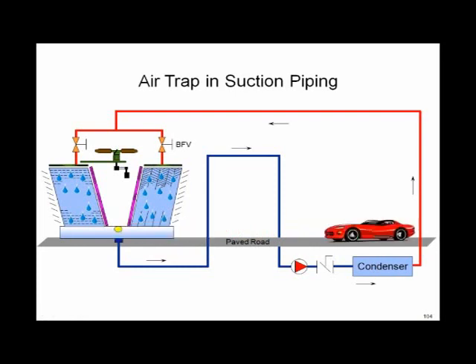I think you kind of got the idea, but the point is, we've got this piece of overhead piping overlooking the road and going back down, and when you turn the pump on, what happens? I hope you recognize that that tower is open. So how are you going to make this work? Well, they called me up and said, get out here, Chris, fix this pump of yours. It won't even pump. We can't even get water to it. I get out there, everybody's kind of laughing. They see the problem. But obviously, you turn this pump on, there's no water above the road. That whole piece of vertical piping there is trapped with air.